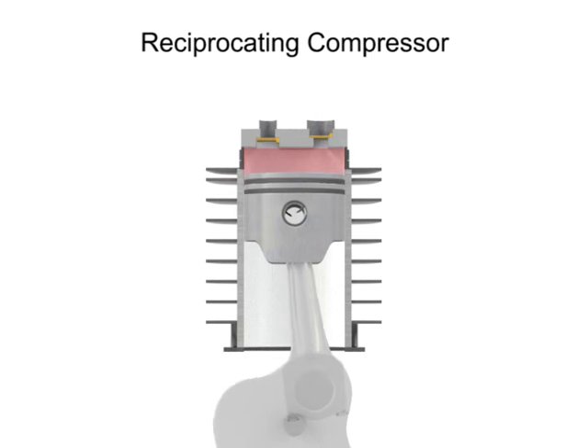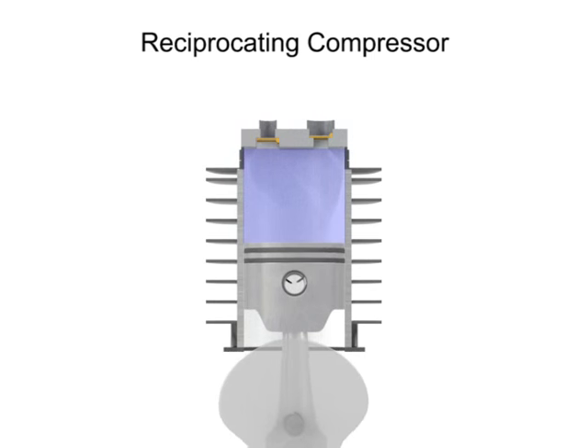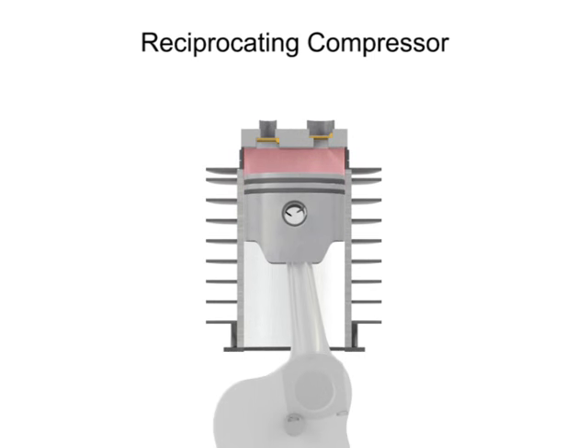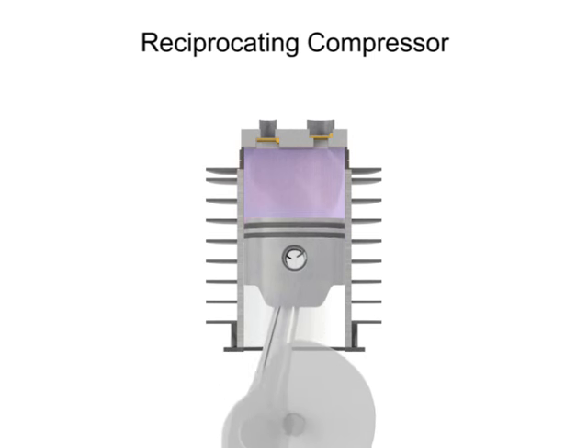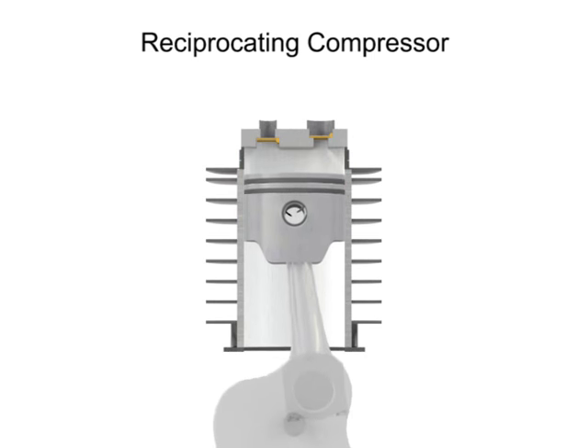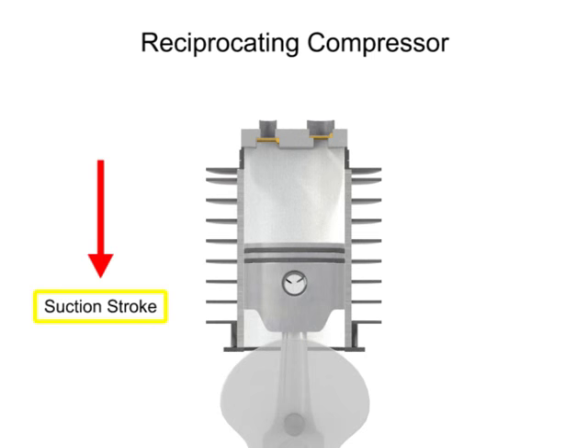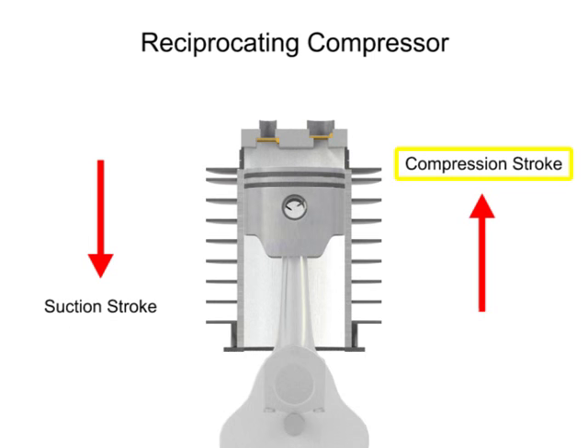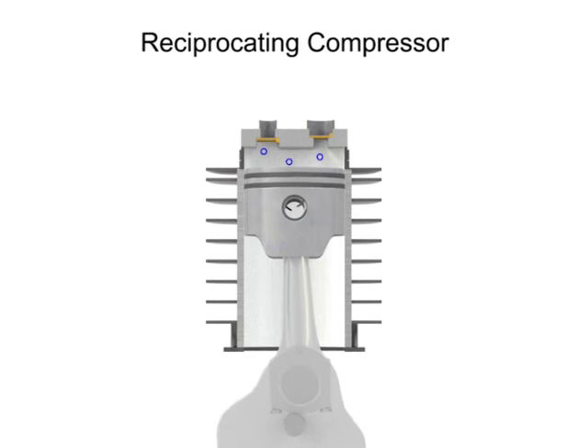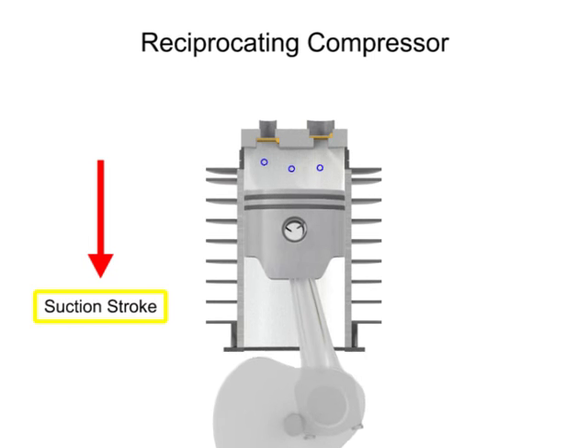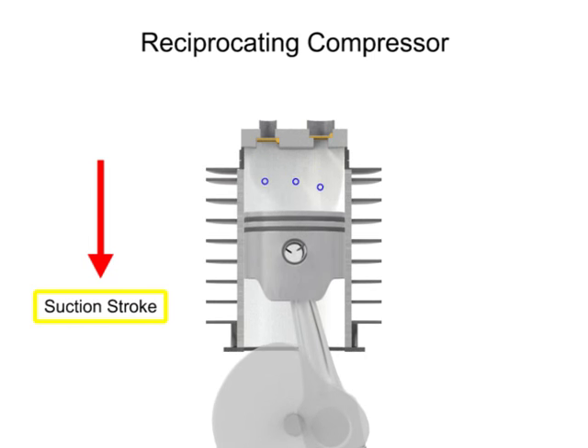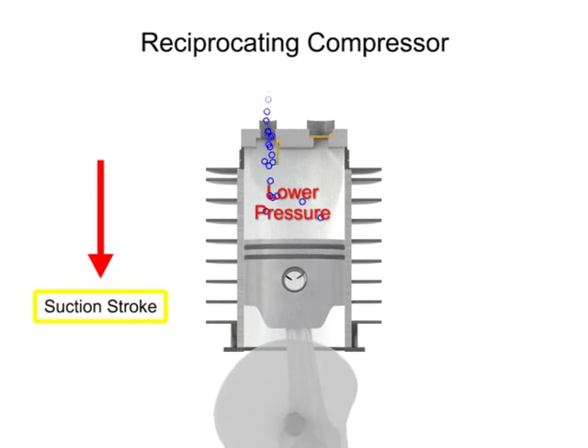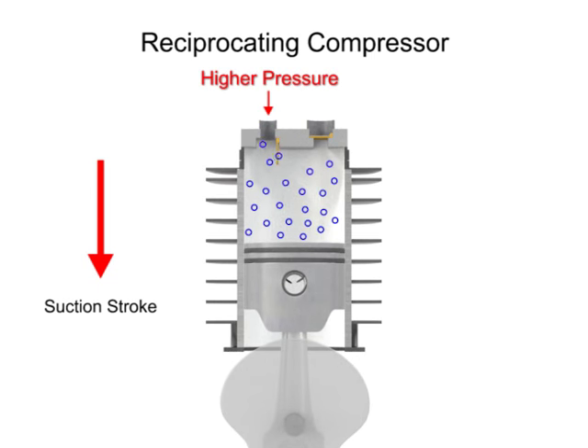As the crankshaft turns, the piston lowers and raises, changing the available volume within the cylinder. The downward stroke of the piston is called the suction stroke. As the piston moves downward, the volume increases within the cylinder. As the volume increases, the pressure within the cylinder becomes lower than the inlet air pressure, allowing the higher pressure outside air to push open the inlet valve and allow more air into the cylinder.